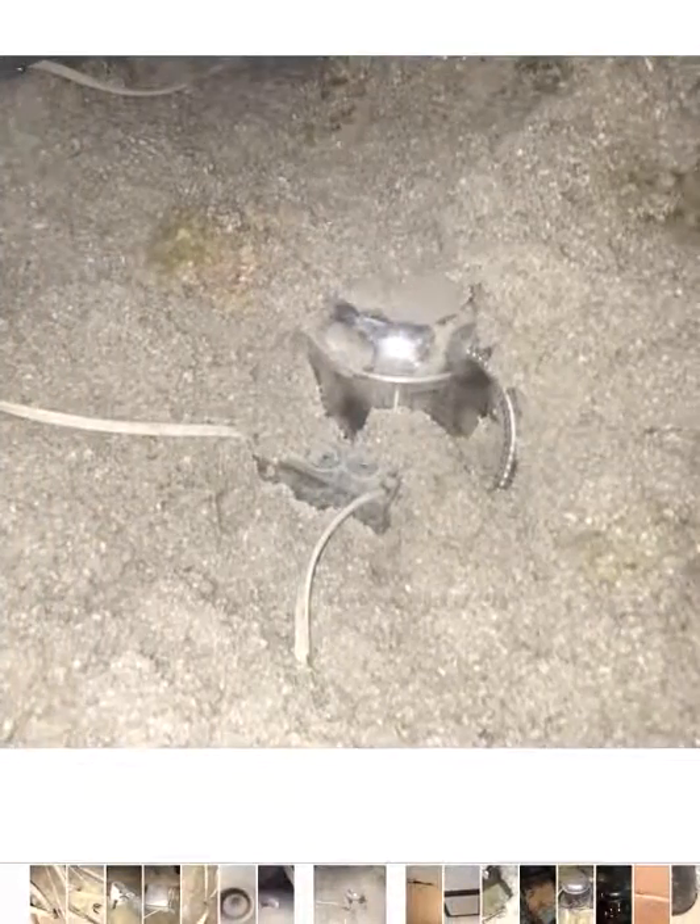There's a can light that's not been properly sealed. That's a fire hazard — it's a dirty mess. That is not proper, so I take a picture of that.